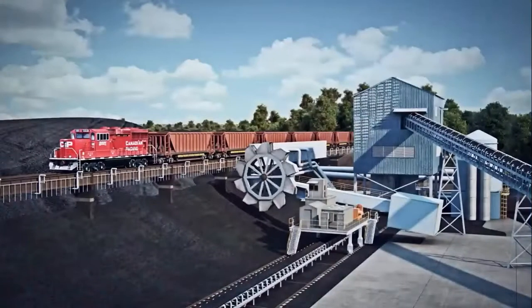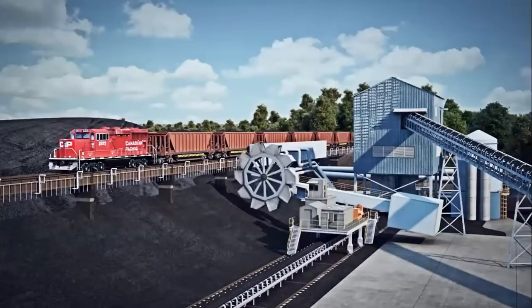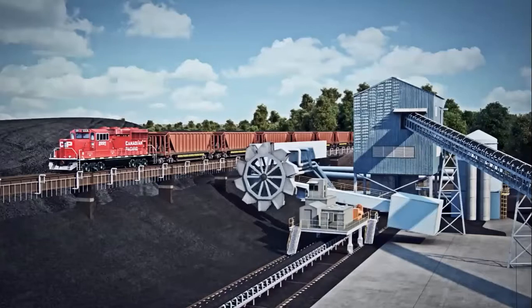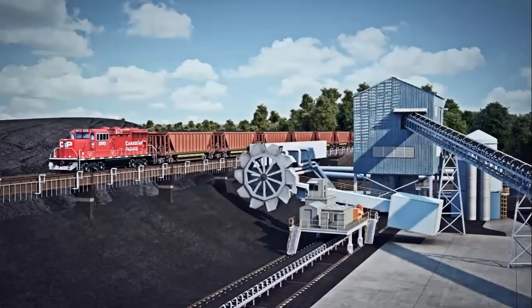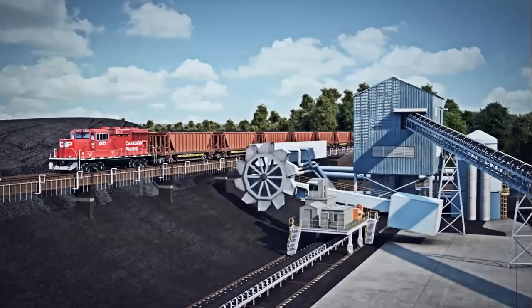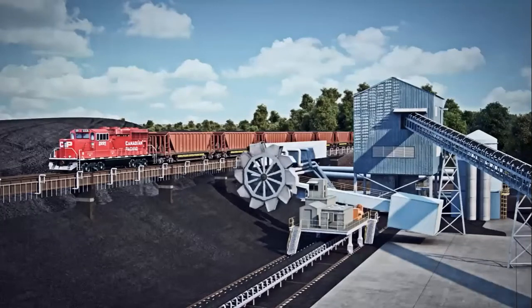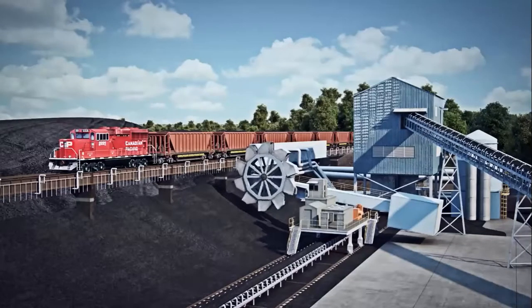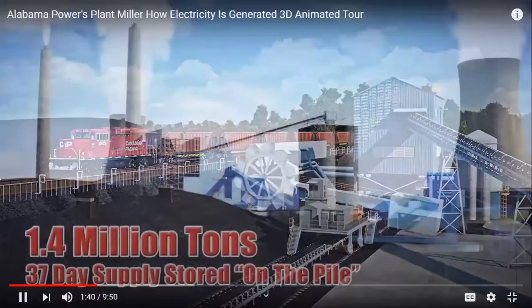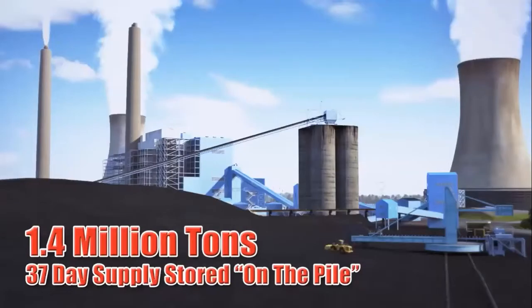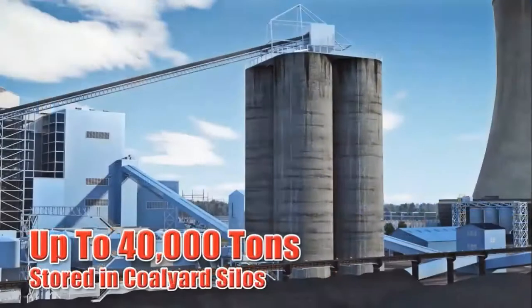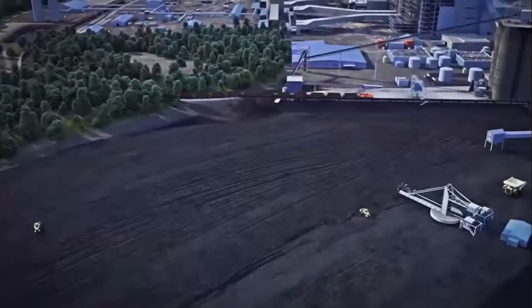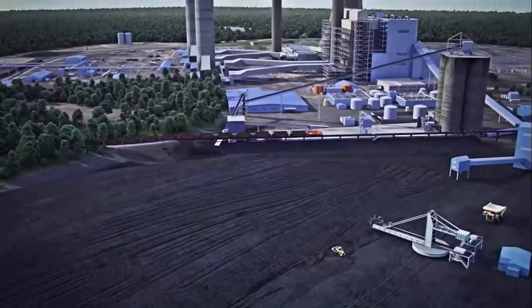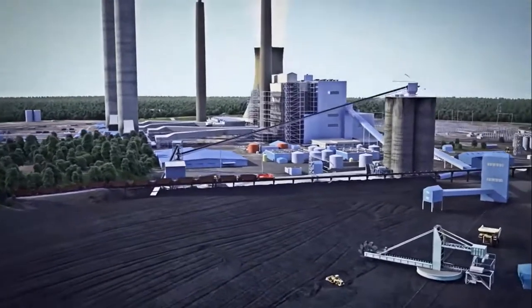Our process uses Powder River Basin coal from Wyoming, a sub-bituminous type coal, as a fuel source. When the coal arrives at our plant by train, we use a trencher and a series of long conveyors to stack coal in our yard, move it to storage silos, or send it directly to the plant. We try to keep a 37-day supply of coal, about 1.4 million tons, on the pile in our coal yard, and up to 40,000 tons in silos. Since we burn as much as 38,000 tons of coal in a 24-hour period, we need to ensure we have a substantial amount on hand.